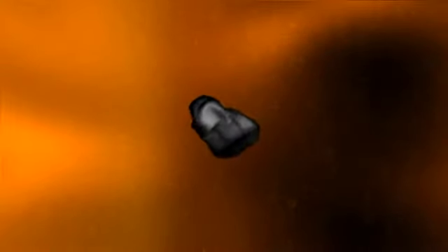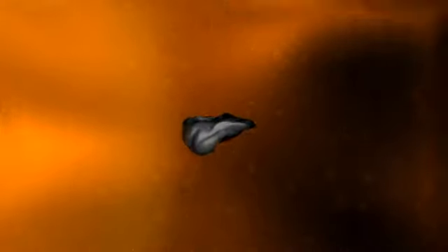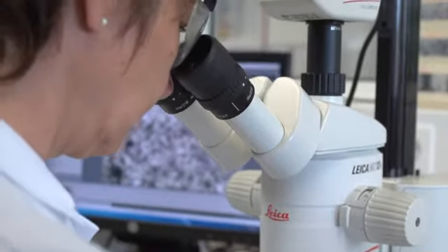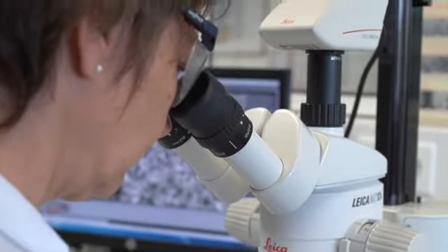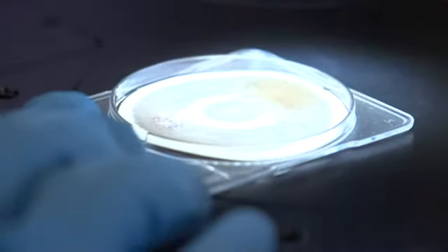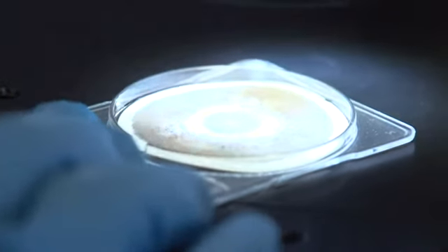When several molecules of this type combine, oil sludge is created. This sludge collects in gaps and causes valve failure. This can even shut down the entire system. Our experienced lab staff analyze oil samples every day, verifying the concentration of oil sludge in the system.